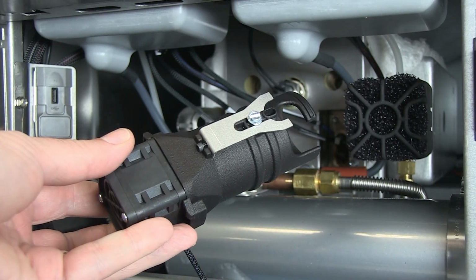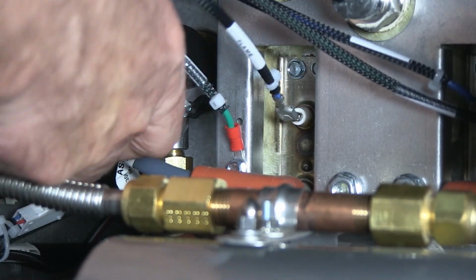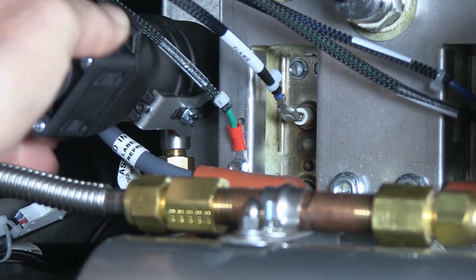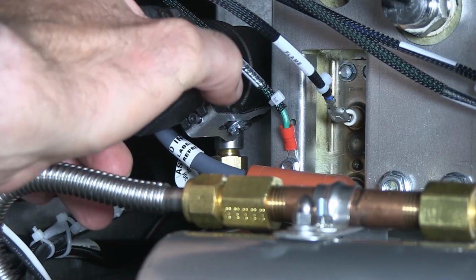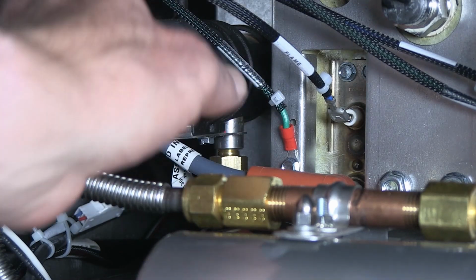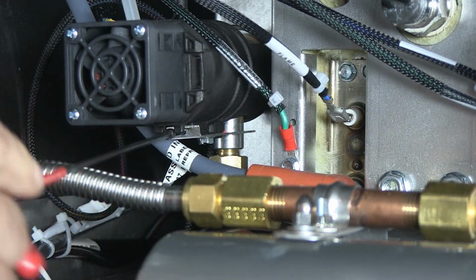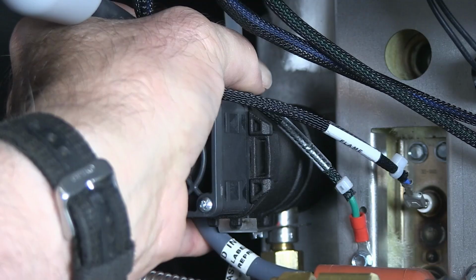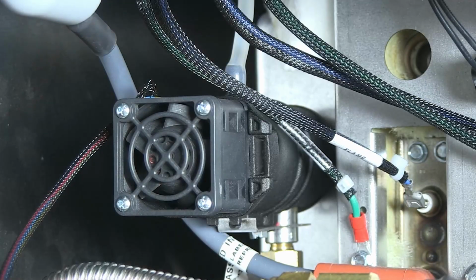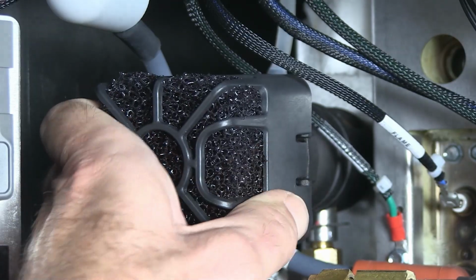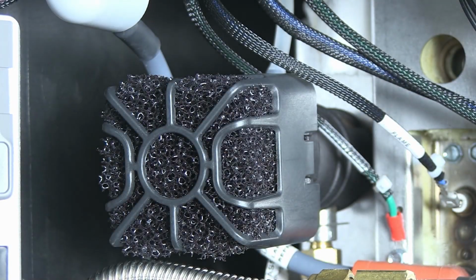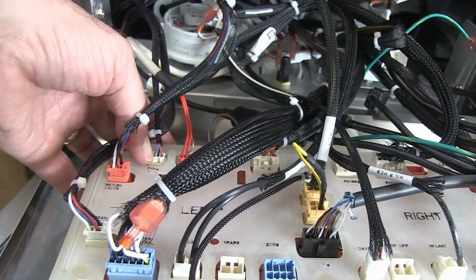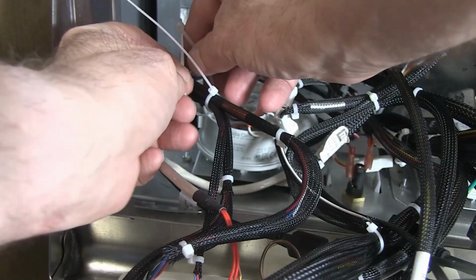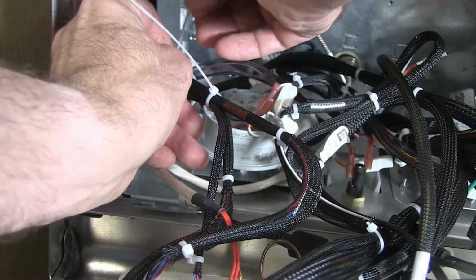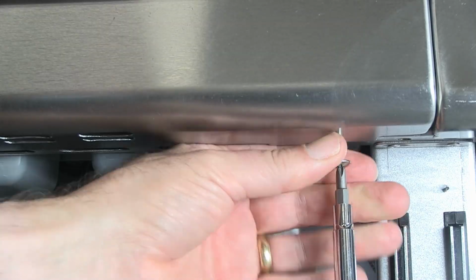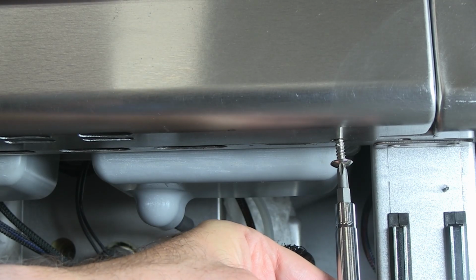To position a new fan, ensure the bracket is forward. Push the assembly onto the burner, ensuring the notch is aligned with the gas line. When the assembly bottoms out against the gas line, rotate clockwise. Tighten the Allen screw to position the bracket around the gas line. Reposition the pressure switch tube. Replace the air filter. Route the fan's wire to the control box and plug it into the HCB. Secure the fan wire to the adjacent wiring with wire ties. Replace the bezel. Run the onboard calibration for the new fan.